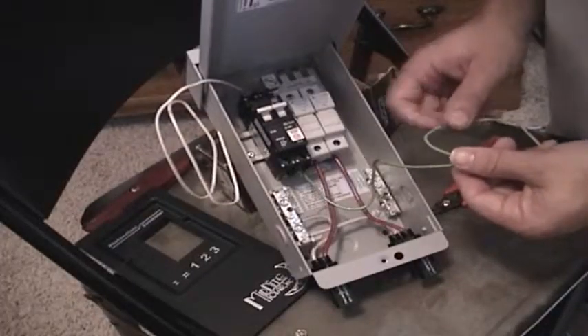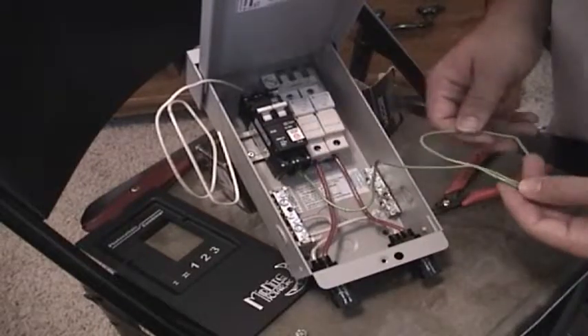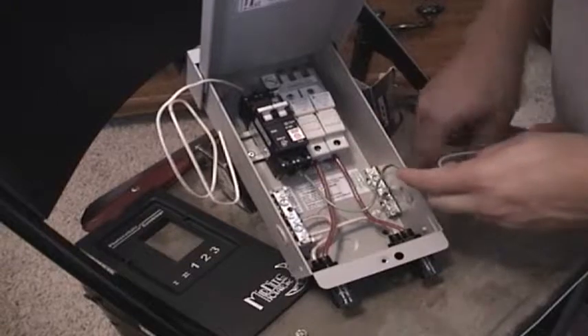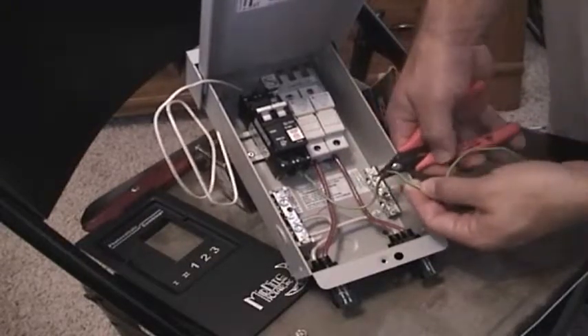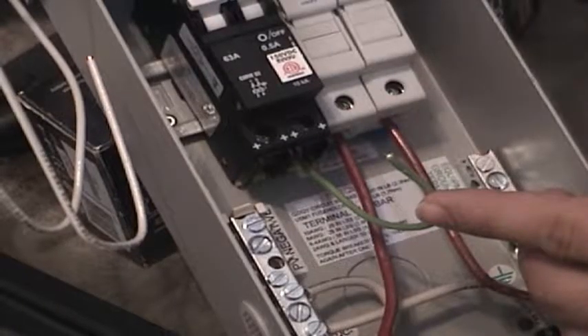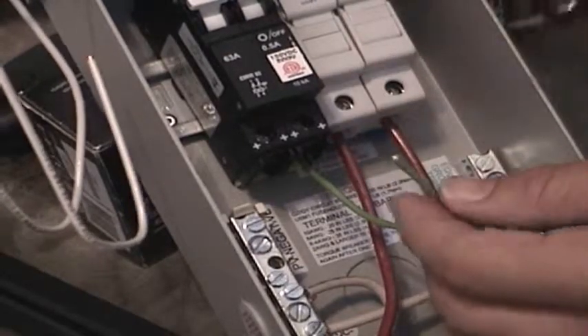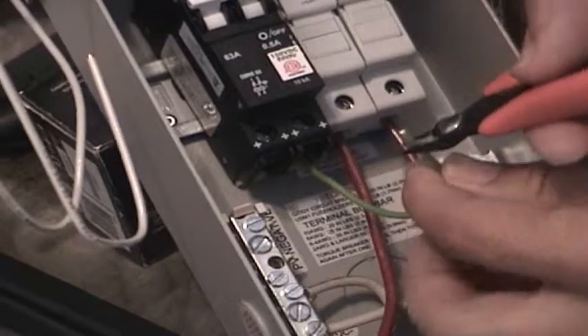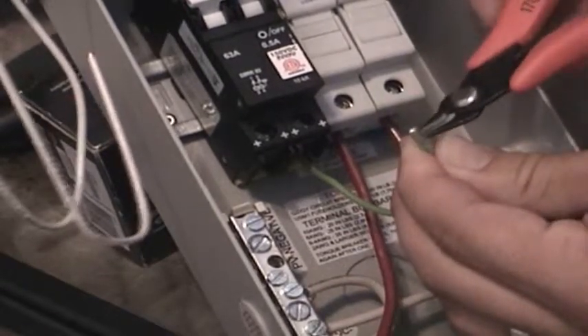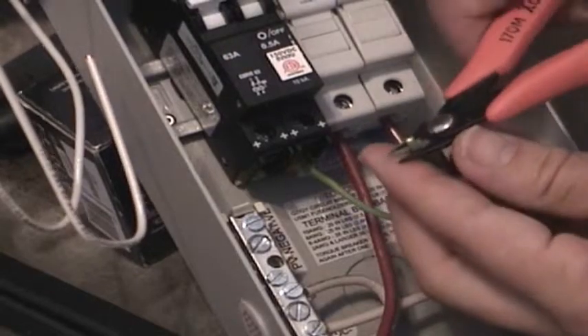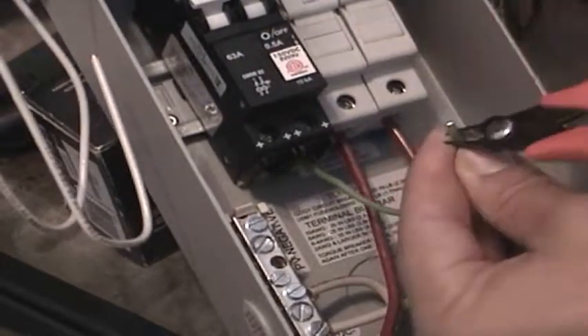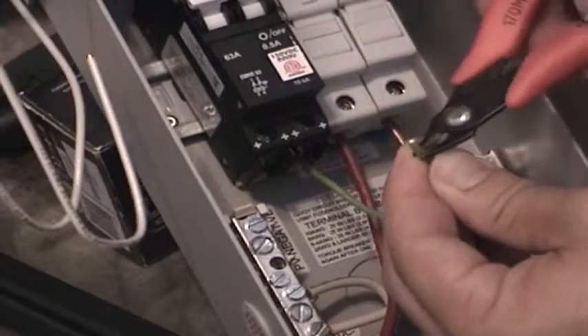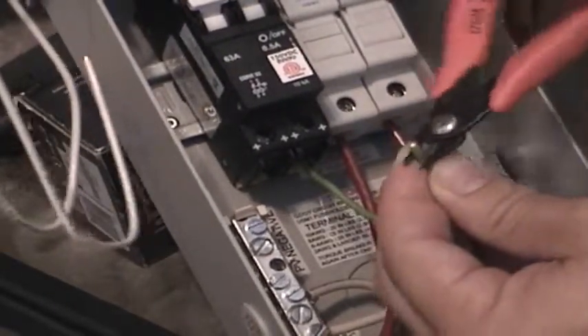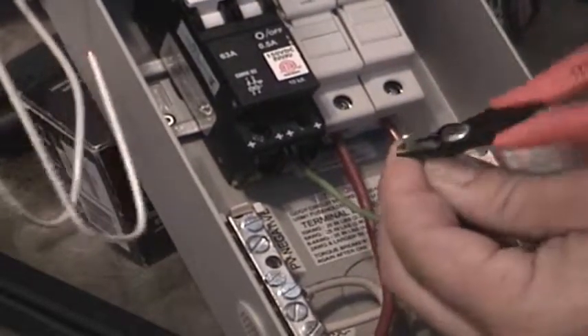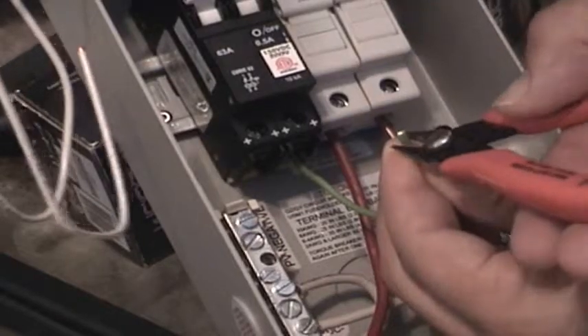Let's begin with the green ground wire coming from the bottom of the GFP device. We only need about 4 or 5 inches, so let's cut off the excess wire with our wire clippers. Now that we have 4 to 5 inches of the green ground wire coming from the bottom of the GFP device, let's go ahead and remove about 1/2 inch of the skin off the end of the wire. You can use the wire clippers to do that, or a utility knife, and again, be careful that you don't cut into your conductor. Just kind of play with it, circle around it a few times, and then use your fingernails to kind of pull it off.